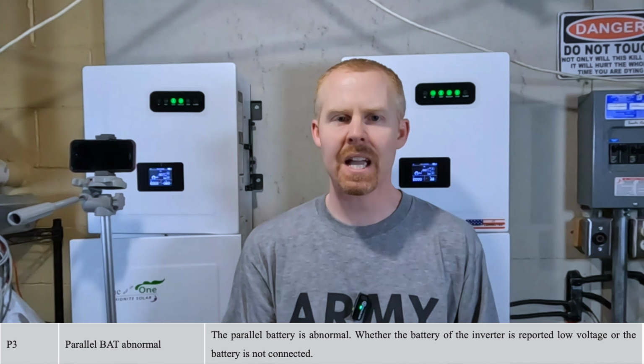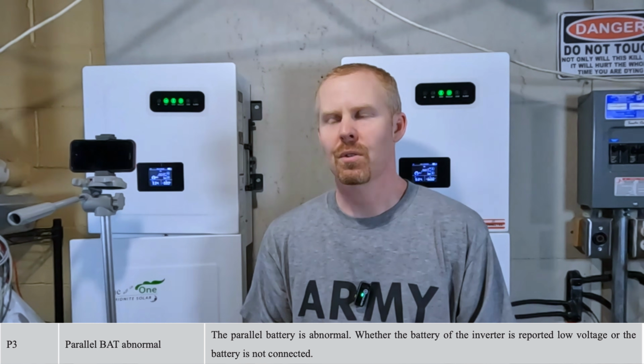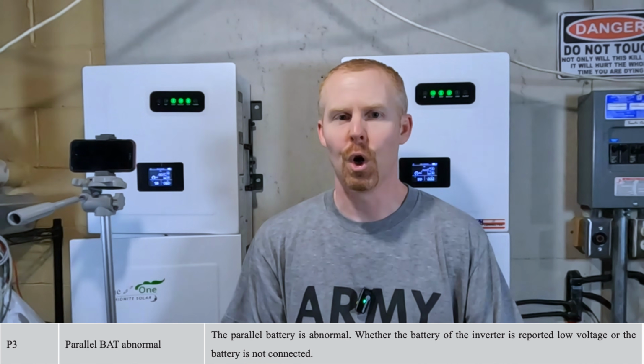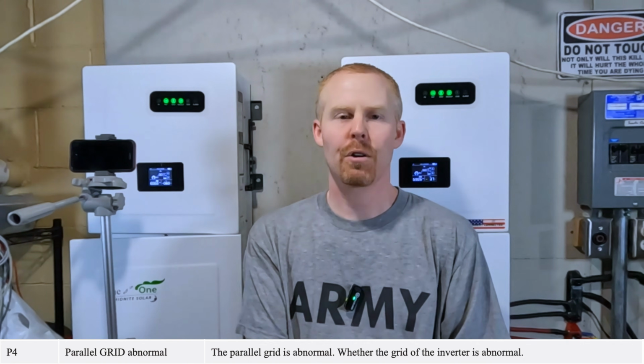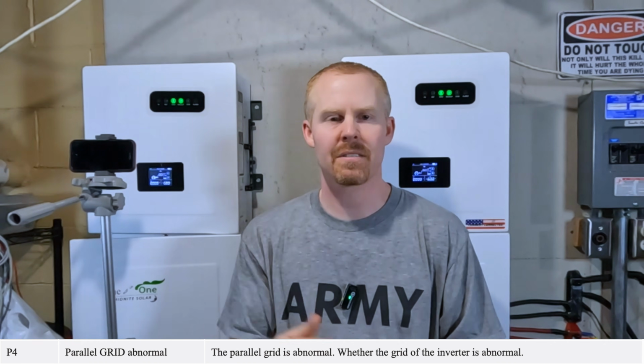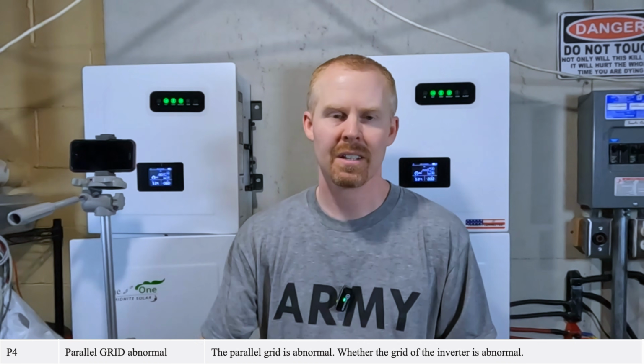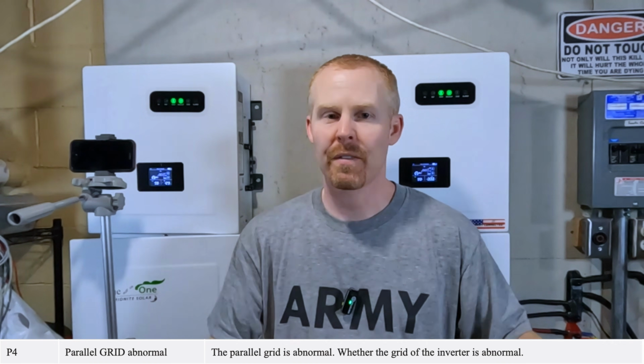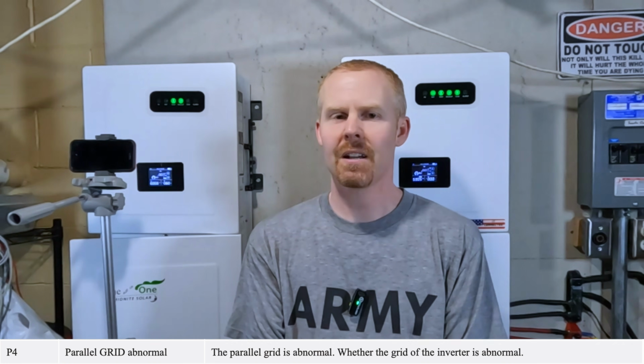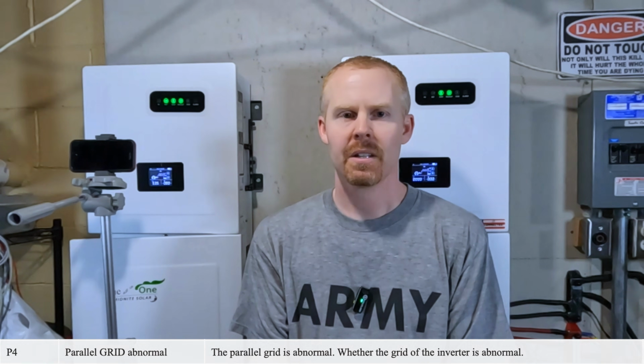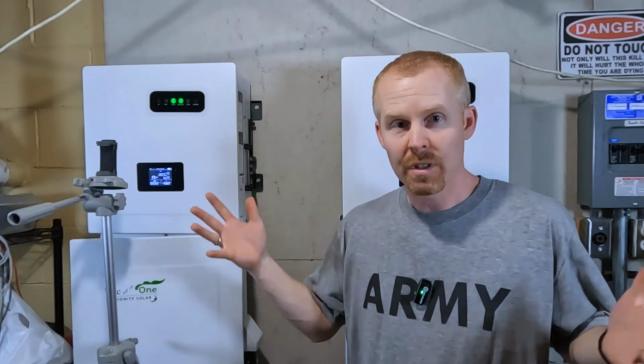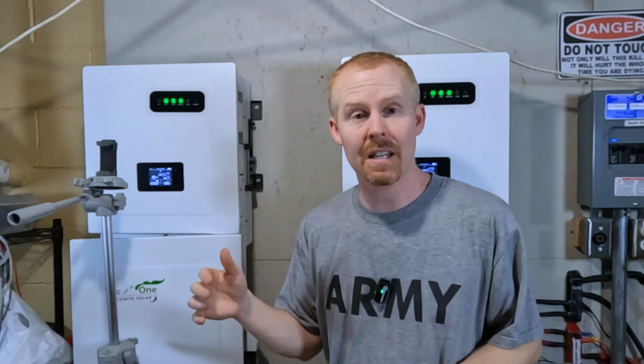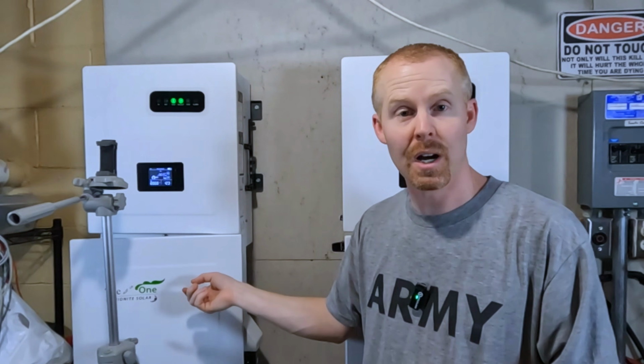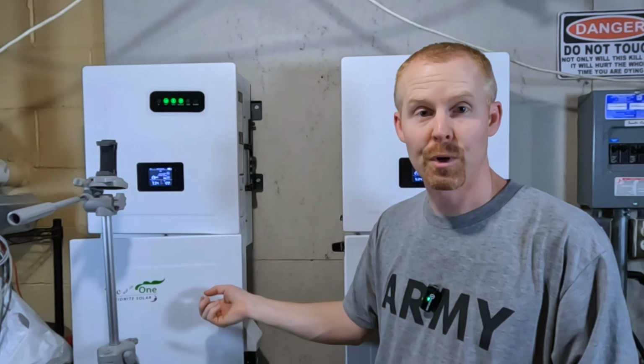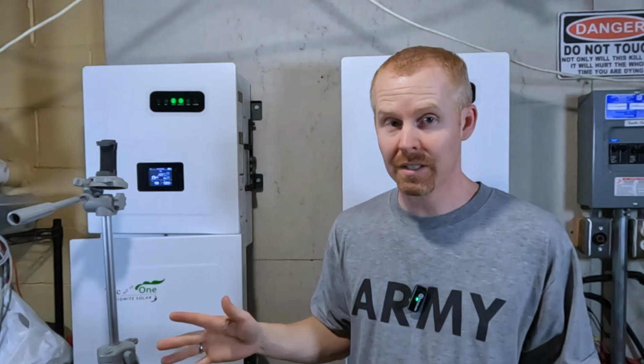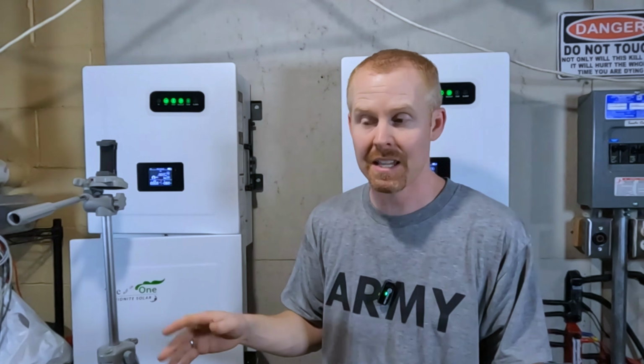A P3 error usually happens when your batteries are low. A P4 error, parallel grid abnormal, usually means that the grid's lost. Maybe you have an outage, maybe you have the breaker turned off. That one, to my knowledge, will not prevent you from starting up the inverter. So these inverters should be unique in that if you actually flip the breaker and turn off the output on one inverter, the other inverter will still continue to power when it's in a parallel state.